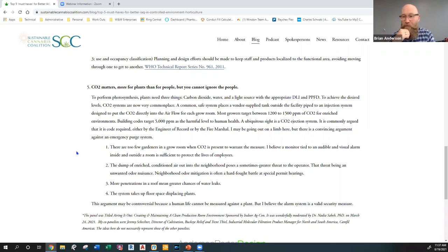There are fail safes that can cut CO2 to the facility, so that if any one room needs it, you can simply cut CO2 delivery because it's a tank outside. We're not talking about wheeling carts, people pushing CO2 tanks with a solenoid valve on them around through the corridors in a hand truck. Those days are past. CO2 is going to be in a tank outside.